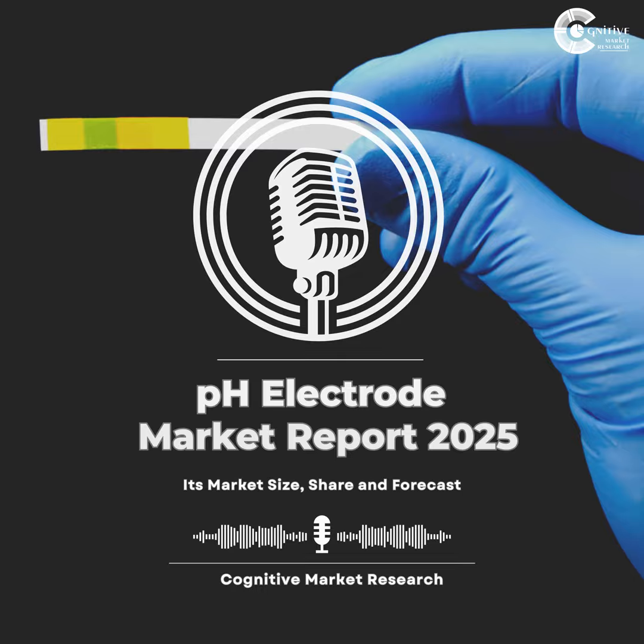That's another significant limitation, yeah. The sometimes short lifespan of electrodes under really harsh conditions. Exposure to extreme pH levels, very high or very low, high temperatures, abrasive particles in the liquid, or aggressive chemicals, all of that can degrade these sensors prematurely. Think about trying to measure pH in something incredibly corrosive like hydrofluoric acid, or even in very low conductivity samples where the solution itself barely conducts electricity.